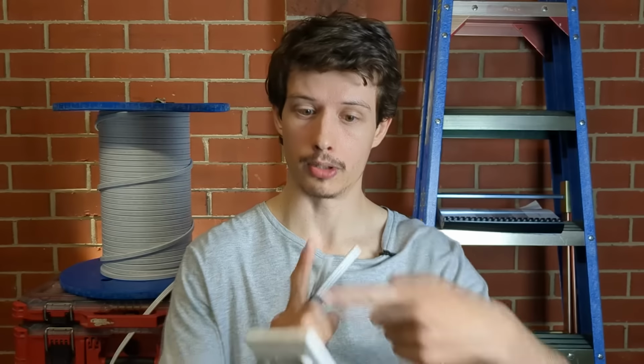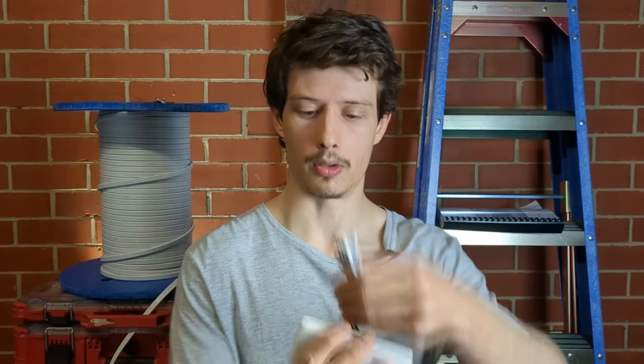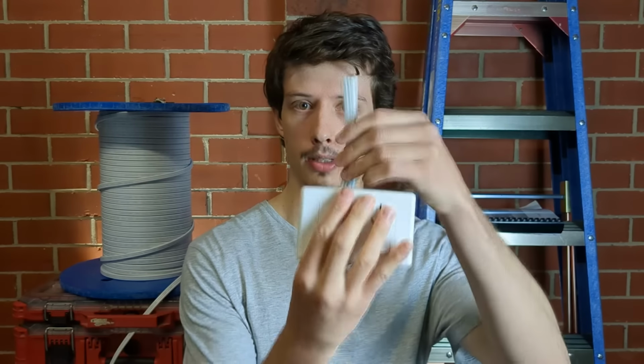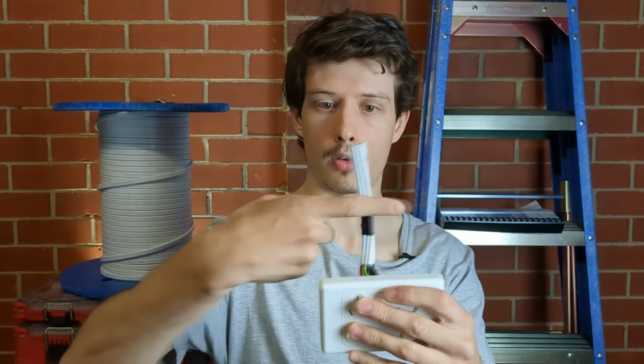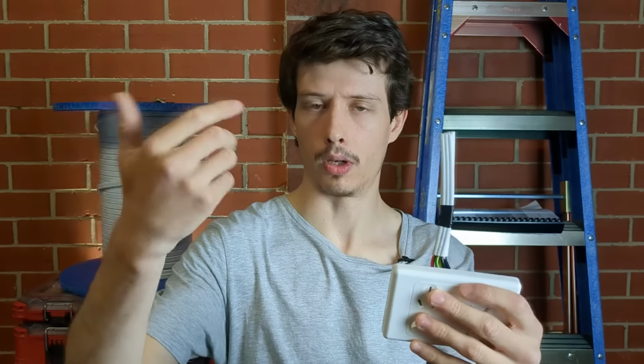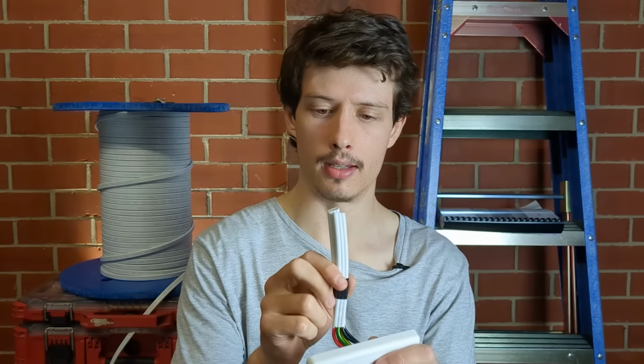You will have sparkies out there that tell you you're allowed to cross them. For example, we've got the power cable coming down the wall, and we've got data crossing behind it or in front of it in the wall. You'll have sparkies that will tell you that's allowed because the electromagnetic field that the TPS creates doesn't interfere with that Cat6 cable. Well, I'm just going to tell you now that's actually kind of bullshit, and I don't know where that started. There's nowhere in the wiring rules that state that you can cross paths.